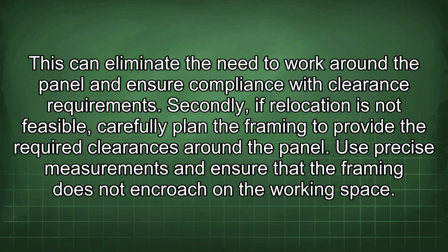This can eliminate the need to work around the panel and ensure compliance with clearance requirements. Secondly, if relocation is not feasible, carefully plan the framing to provide the required clearances around the panel. Use precise measurements and ensure that the framing does not encroach on the working space.